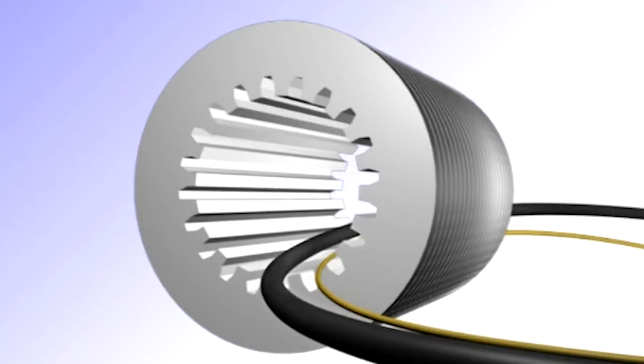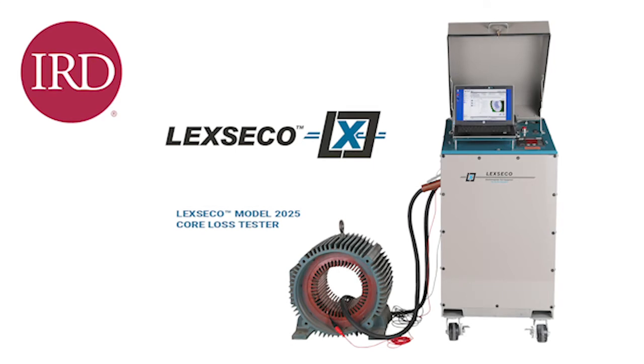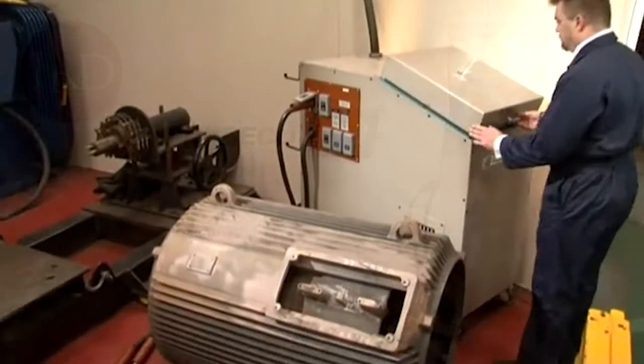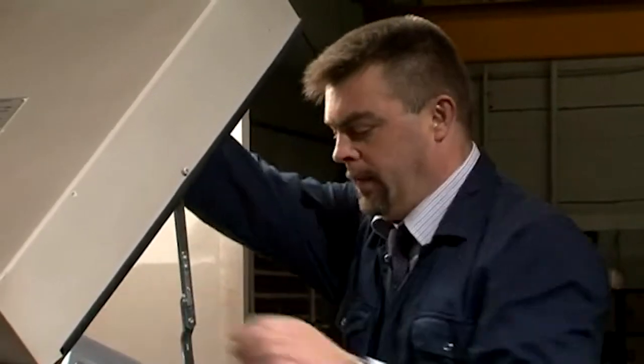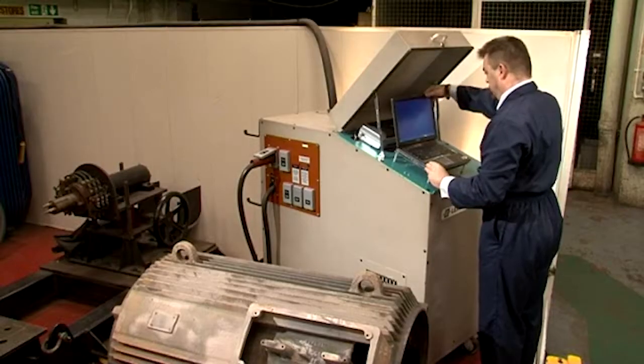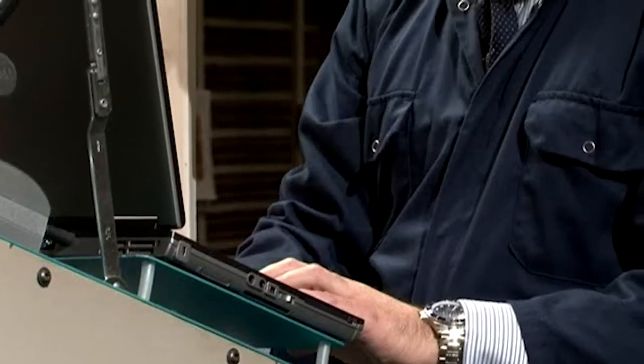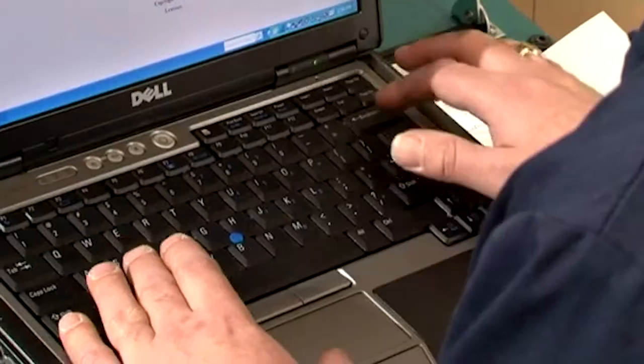The process can also be used to identify the position of any hot spots. The IRD EL CID family of core loss testing products available in a range of capacities is the leading solution providing end users and motor repair organizations with a quick and efficient process to determine the condition of cores during inspection and repair procedures. This testing provides assurance of system performance and integrity on completion of repairs and rewinds.